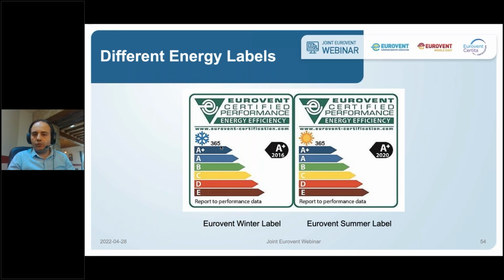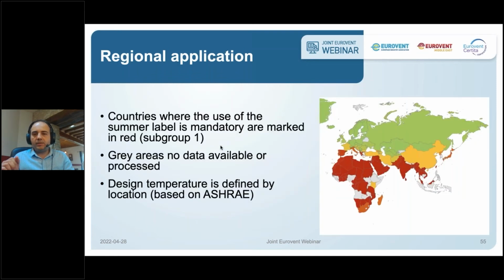So you have two labels for a unit, and depending on the regions, it is mandatory or not to display the summer label. We have defined what we call the subgroup 1, which defines the hot and humid climates. And for the subgroup 1, it is mandatory to provide the energy classification in summer conditions.